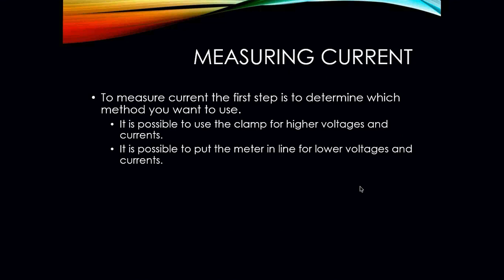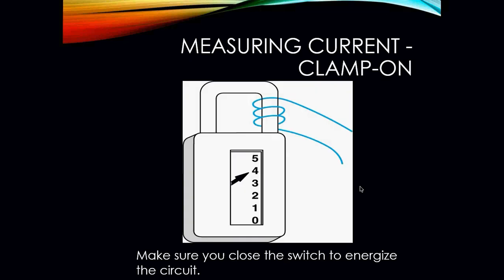Okay, to measure current, the first step is to determine which method you want to use. Okay, you can use your clamp-on for higher currents, or you can use an inline amp meter for taking lower currents. This here is an example of your clamp-on meter. Okay, make sure you close the switch to energize the circuit when you're taking a clamp-on amp reading. Otherwise, again, if you have no power, you're not going to get any sort of amperage.